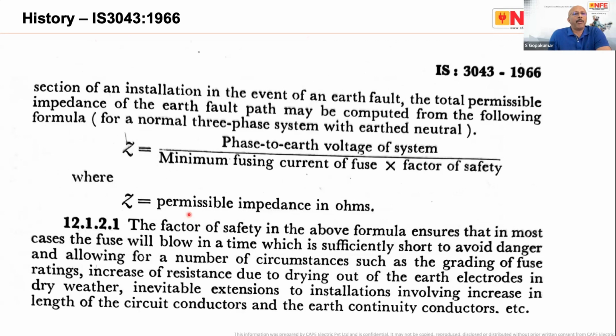Also, in the same clause 12.1.2.1, the calculations are given. Z means fault loop impedance: the phase to earth voltage of the system divided by the minimum fusing current of the fuse, into the factor of safety. Currently, if we look at the 2019 version of IS 732, the factor of safety is about 33%. I will show the calculation later on. What I wanted to explain is that this is not a new subject. It has been there in our standards and regulations since the old days.